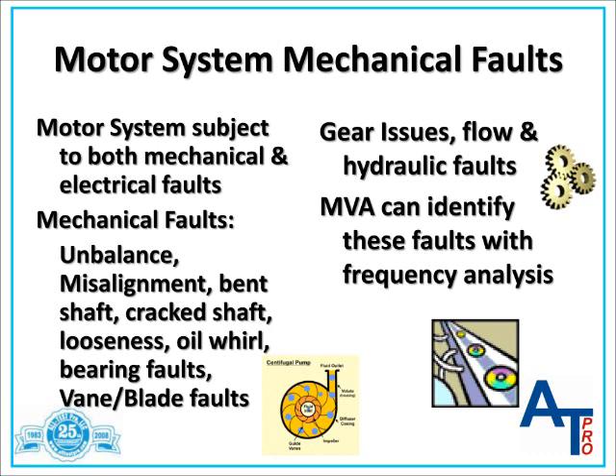These hydraulic or mechanical faults create forces which are applied from the shaft to the bearing and bearing support. These forces cause the bearing housing to periodically move at the frequency of the applied force. The amount of motion depends upon the strength of the applied force, as well as the mass and stiffness of the structure. Because of this limitation, early indications of many faults remain undetected, and several measurements are required at different locations on the motor system, usually at the bearings, to identify developing faults using vibration analysis.